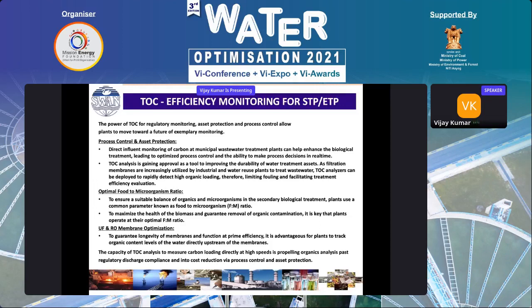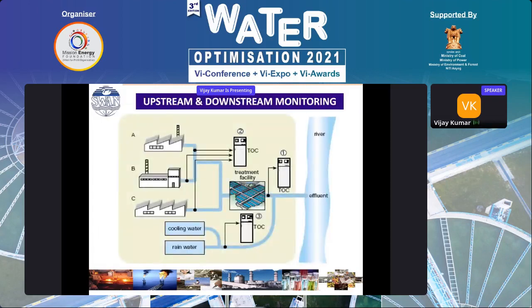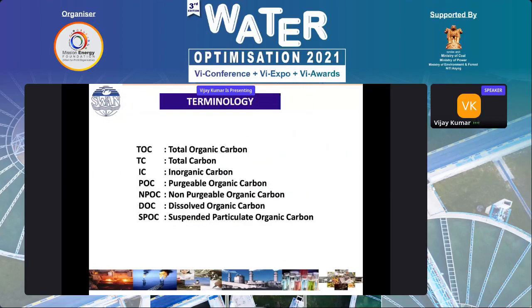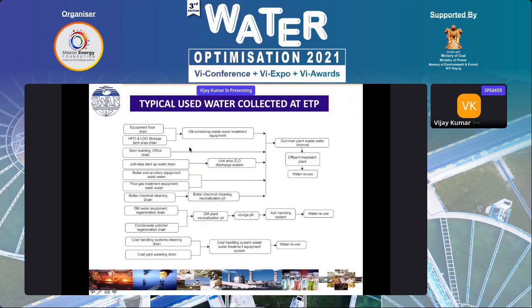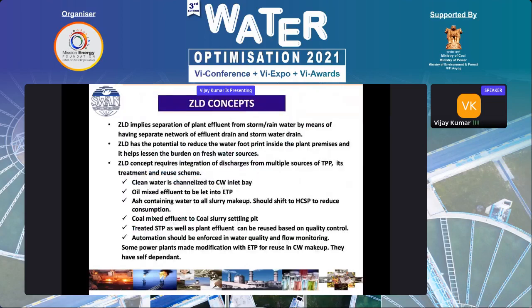Again, in wastewater optimization, process monitoring and asset protection, TOC has a great role. You can see upstream, downstream, or in a typical power plant, as I explained these different areas: oily water goes to the ETP, then ZLD. Unit startup water drain goes to the ZLD discharge system and ETP. Boiler ancillary equipment wash water and flue gas treatment wash water go to the ETP. Boiler chemical cleaning drain goes to the neutralization pit, then to the ETP. DM water equipment regeneration and condensate polisher regeneration drain go to the DM water neutralization sludge pit, then the ash handling system and water use system. The coal handling system cleaning drain goes to the coal yard wash drain. So in all these areas you can use TOC and optimize your treatment plant.